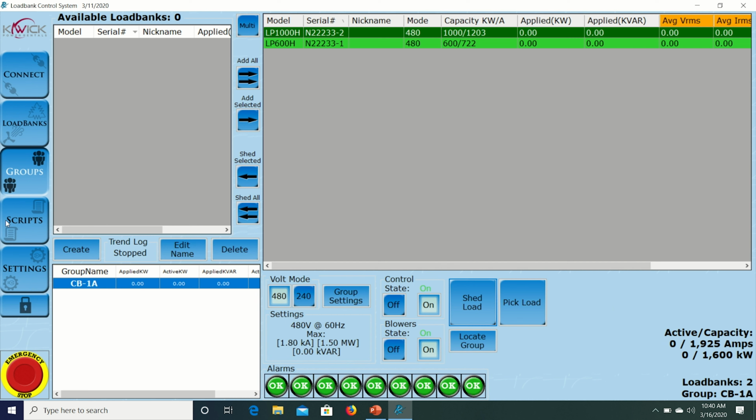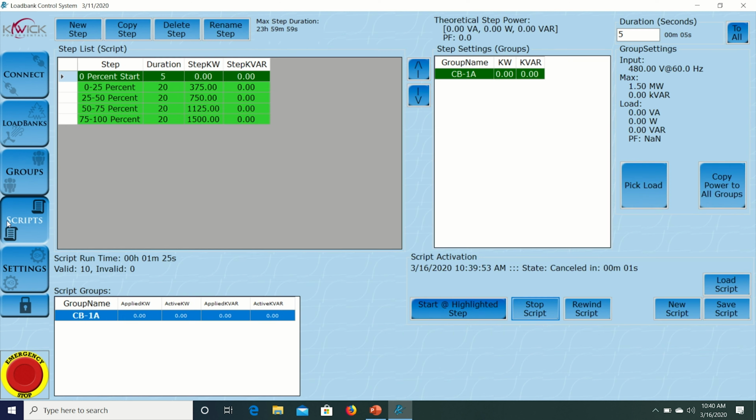When you go to restart your test, the step that you start on will start from the beginning of that step. If you were in the middle of a 2-hour burn at a specific load and stopped an hour into it, it doesn't pause and restart with an hour left to go. It will start again at the beginning of the duration of that step. You can easily adjust the duration of the step and then continue if that is what is desired.